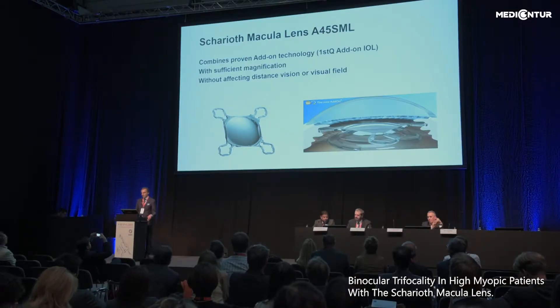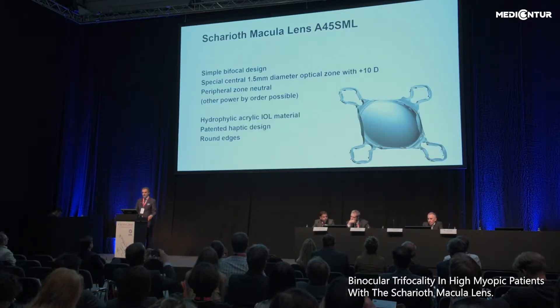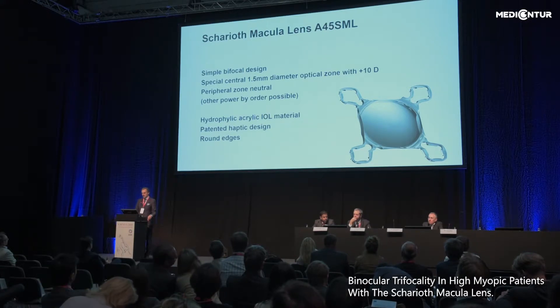The Scharioth Macula Lens is based on this add-on platform. It combines the proven add-on technology with sufficient magnification without affecting distance vision or visual field. It has a simple bifocal design with a special central optic of 1.5 mm and about 10 diopters of addition. The peripheral power in the standard version is 0 diopters but it can be ordered in any diopter. It is a hydrophilic material with round polished edges and a patented haptic design.